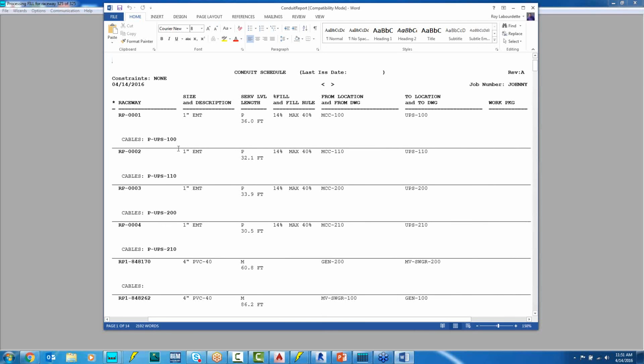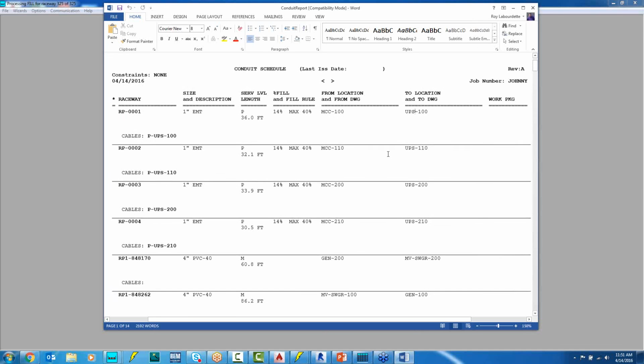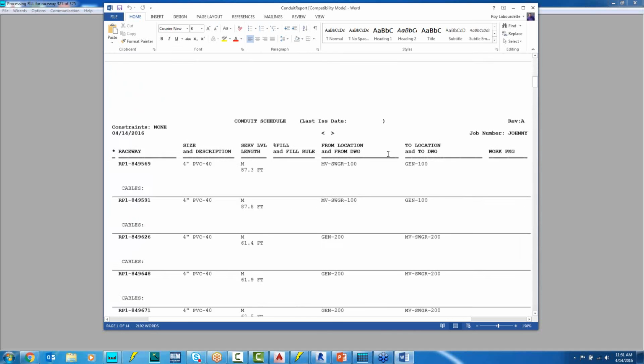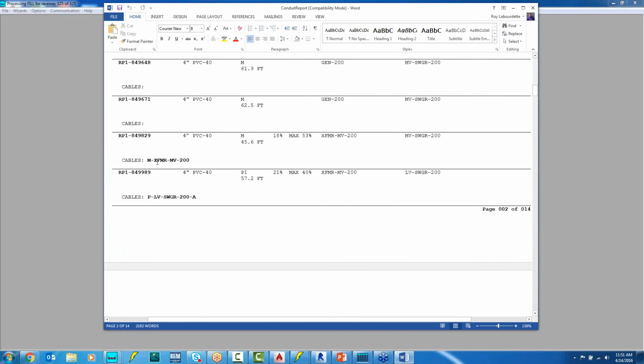So this particular conductor is a UPS feeder. It's got a maximum fill of 40% because it's probably 3 or more conductors, and it is actually filled 14% of this 1 inch EMT, and it's going from the MCC to the UPS. As I scroll down, I can see the conduits that are in my project. This is a multi-conductor conduit, so there's only one cable jacket, which allows me a maximum fill percentage of 53%. And since it's an underground duct bank, I wanted it to remain and lock at a 4 inch PVC, so it's only 18% full.